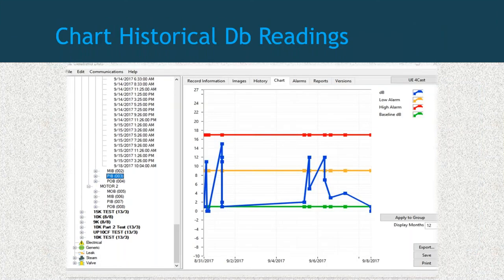We can chart the dBs over time and get a visual representation of the history and the condition of that motor or that bearing. We can look at it versus baseline, see if it's hit a low alarm, see if it's hit a high alarm.